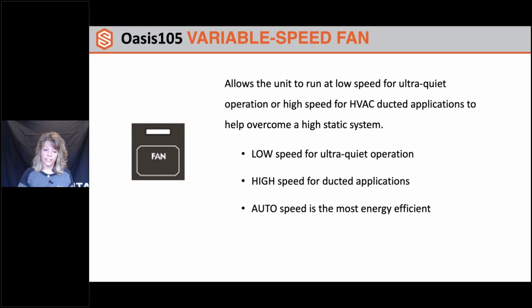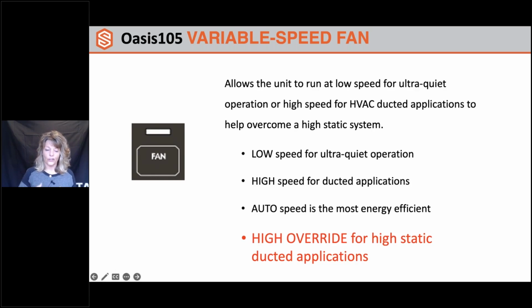when it is ducted. When we're going to duct this unit, we're going to put it into high, and that is going to help us up to a static of about 0.4 when we use that high speed. Now, what's really exciting about this unit is there is a fan override for high static ducted applications up to 1 inch. There are no other ducted dehumidifiers on the market that can handle that amount of static. So that's very exciting. Typically when you get to 0.5, even 0.6, you're really pushing it, putting a dehumidifier onto that amount of static.